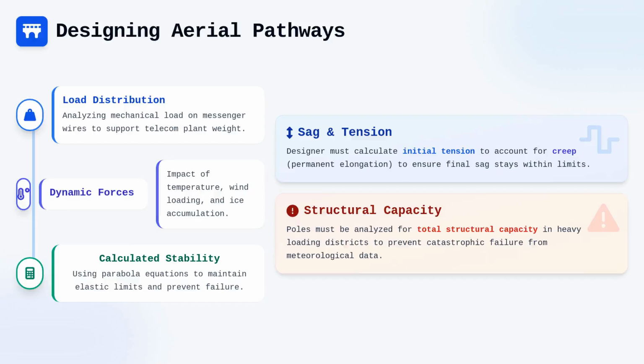The designer's objective is to calculate the initial tension so that, after creep, the permanent elongation of the messenger over time, the finalized sag remains within the prescribed limits. We calculate these values using the parabola equations for spans, ensuring that the messenger operates well within the elastic limit of the material to prevent failure during severe weather events.